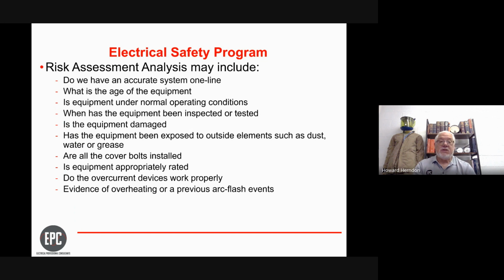Like many other industries, this is very difficult in a lot of facilities because we've had a lot of different remodels over the years, upgrades, downgrades, overgrades, maybe the building has changed its function, whatever the case might be. But having an accurate electrical one line is a requirement of NFPA 70E, and it's required in order to properly do a risk assessment.